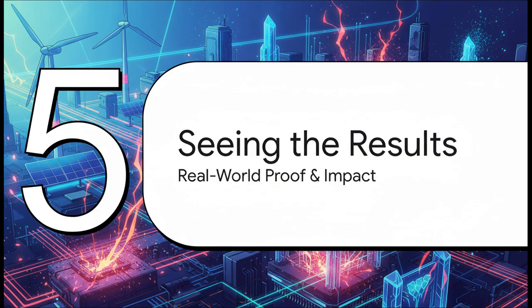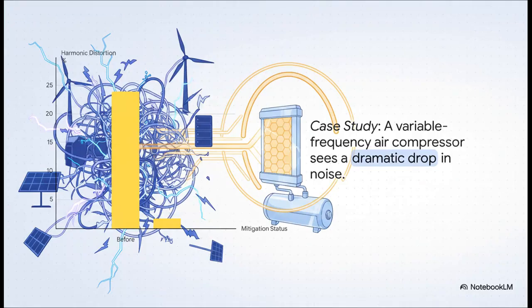So the million-dollar question: does it actually work? Let's look at some real-world proof. Here's a case study on a common piece of industrial equipment. Before installing the filter, total harmonic distortion—a way of measuring all the electrical noise—was at 24%, pretty dirty power. After installing the filter, it dropped all the way down to just 1.74%, a massive reduction in noise.